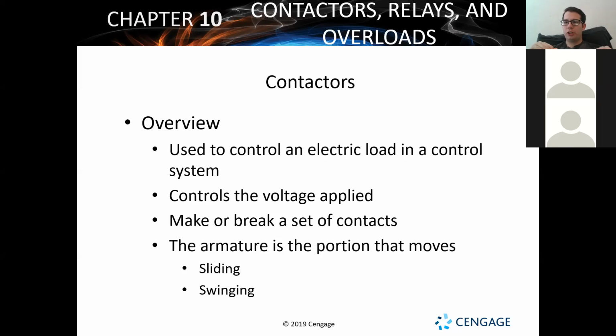If you have a switch and it's open, so it's disconnected, power is sitting here and there's nothing on this side. Where I can test to check for voltage is on these two leads right here, on the two ends of the switch. Inside is where it controls whether or not this actually closes. But basically, these two ends are where I'm going to test it.